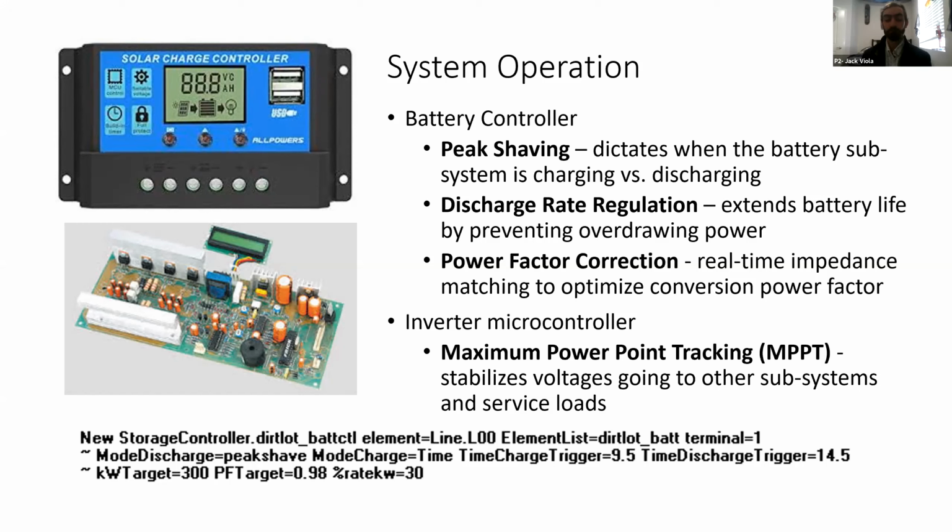applications. A lot of places are claiming that their batteries have 100% battery depth of discharge, which means that they could charge it up to 100% and then discharge it down to 0%. However, I did not include that figure in our models. I used a 95% depth of discharge rate because looking more closely at the research, obviously the chemical reaction is not completely reversible in these batteries, but the 100% depth of discharge is a little bit optimistic still, whereas 95% is a lot safer for actual application purposes for our modeling.